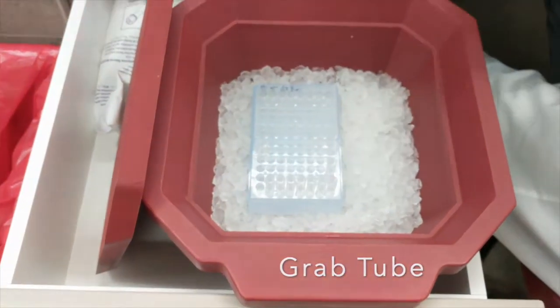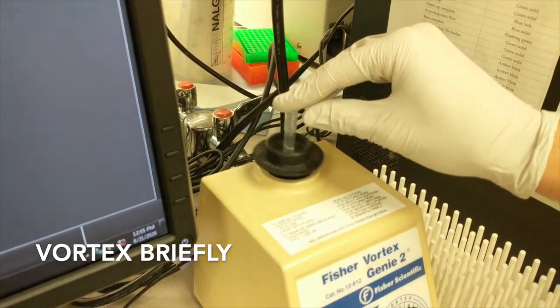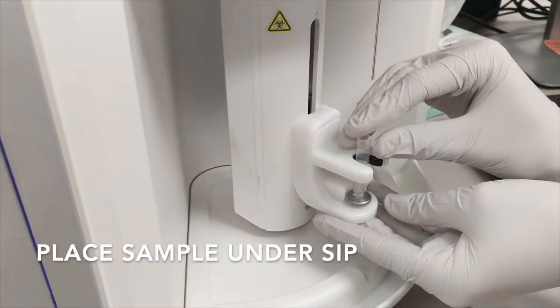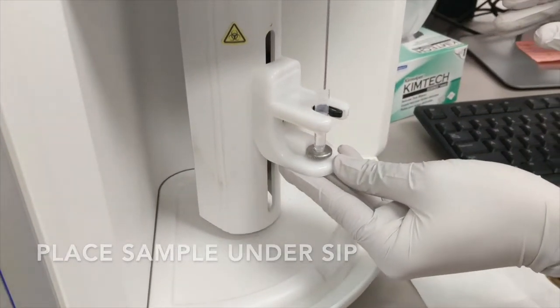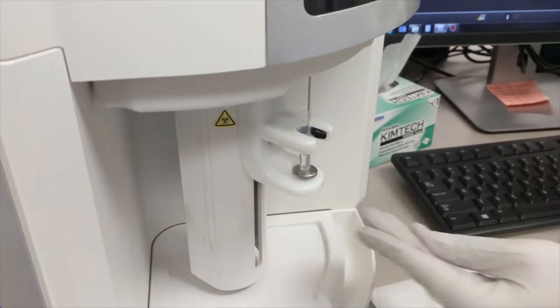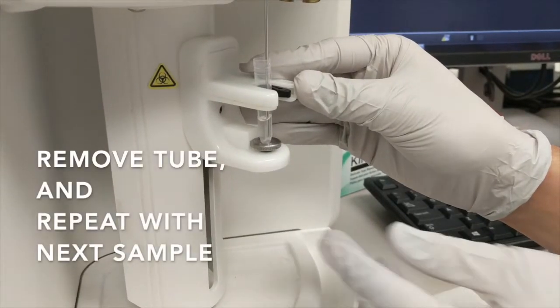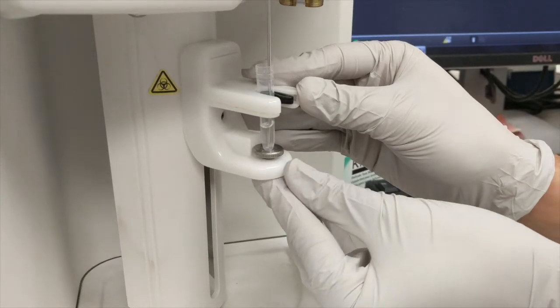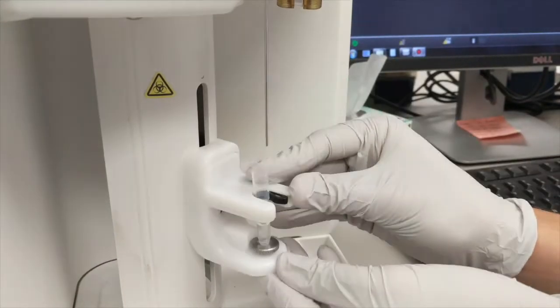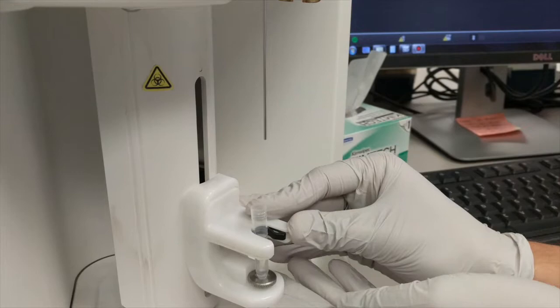Before we show running on the machine, we need to briefly discuss the general protocol for running a sample. To start, grab the sample you wish to run. Briefly vortex the sample to ensure the cells are evenly distributed throughout the fluid, and then place it under the sip. Gently push up on the sample arm to put it into the correct place. When a sample is complete, gently pull down on the sample arm, wipe off the sip with a Kimwipe, and proceed to the next sample.